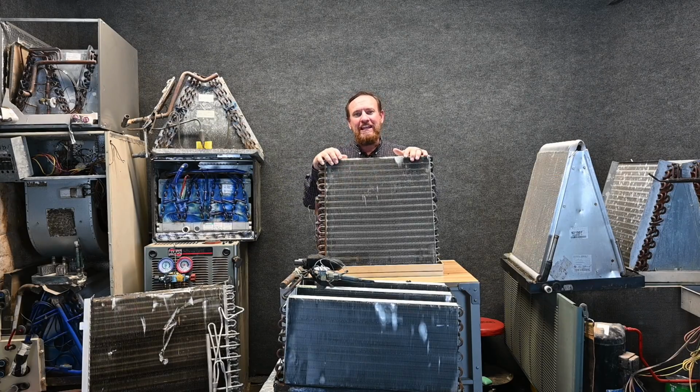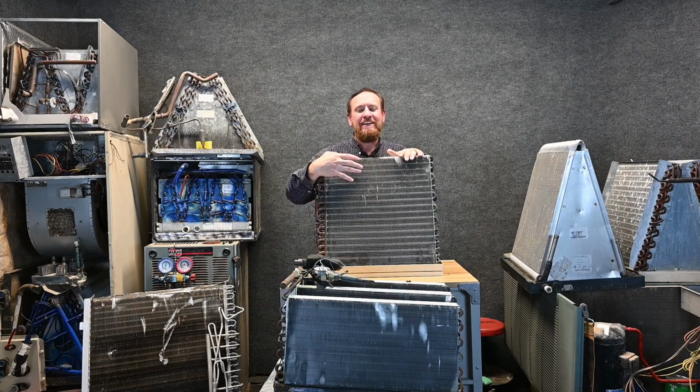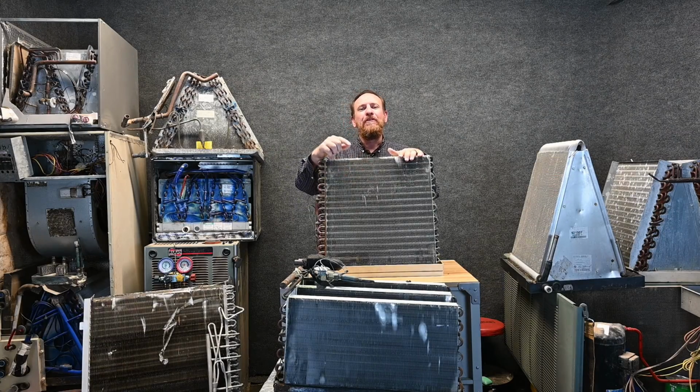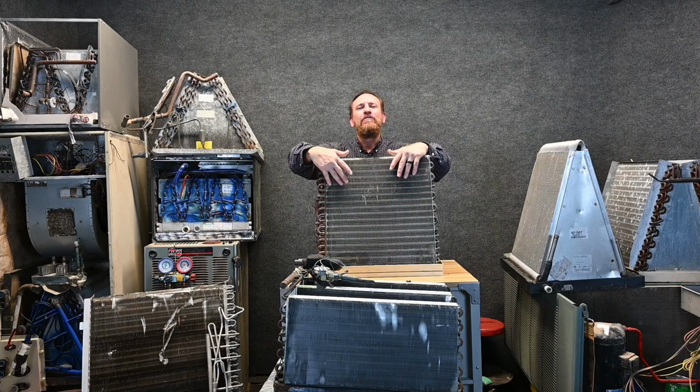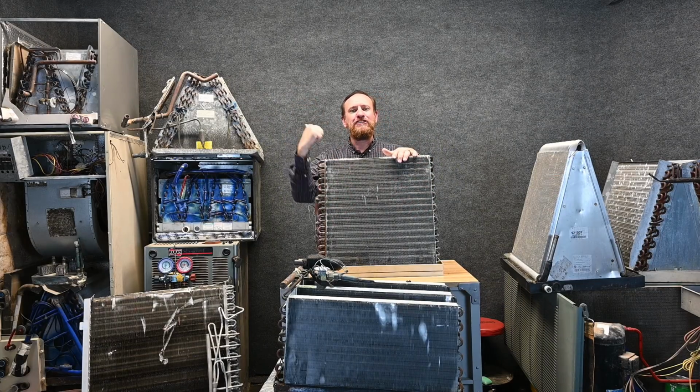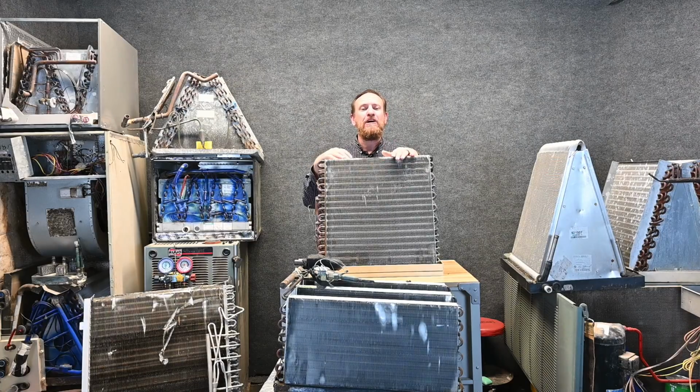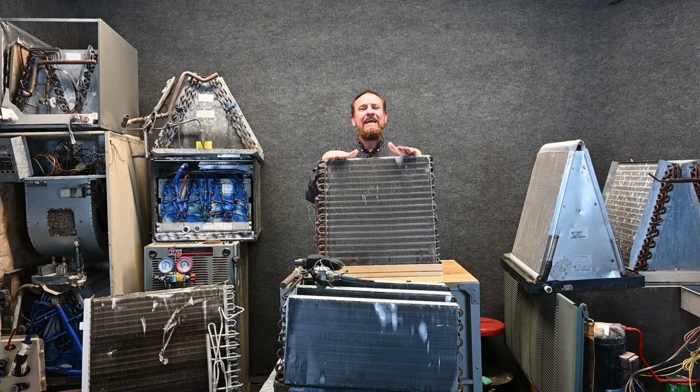If we left the fan in the on position, we're continuously moving air across this evaporator coil. And as we're moving air across this evaporator coil, all that moisture that we paid money to dehumidify, to condensate on these fins, will then re-evaporate back into the air. If we continue to run the air through this, all that moisture that we paid money to collect is now being re-evaporated back into the air and is being distributed through the house. So the humidity in the house doesn't drop as much. So especially in a moist climate, you want to make sure that fan cycles in the auto position. Do not leave it on because it's not going to dehumidify as well.